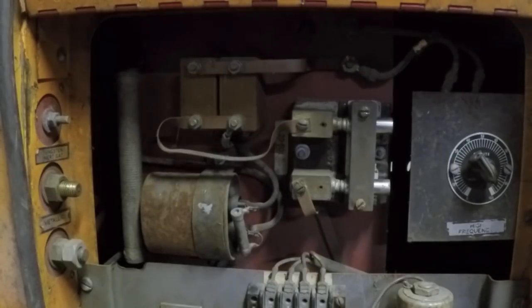It's one of those digital clock, soft touch on-off type circuits. When she was cooking, it suddenly stopped, and when she pressed the button it just said off. My theory is that this welder is generating enough electrical noise on the circuit that it scrambled the computer in the stove. So all I had to do was shut the breaker off and turn it back on, which reset the computer, and the stove is working again. So the stove never lost power, it never tripped the breaker, it wasn't an overcurrent issue. It's that this HF noise bled into that circuit. That's my theory anyway.